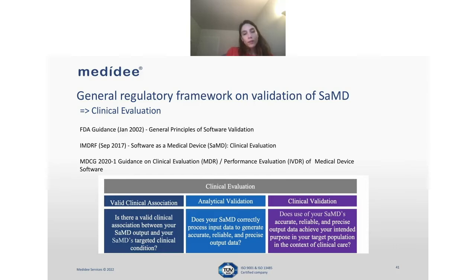And then the third point is clinical validation. I think this is the most straightforward. Here, you're answering the question: does use of your software as a medical device, with accurate, reliable, and precise output as verified with the technical performance verification, achieve the intended purpose for the specific target population in the context of clinical care? So here you're answering questions such as: have I considered in my clinical validation the intended use, the target population, the intended user, the intended user environment, use conditions, etc.?